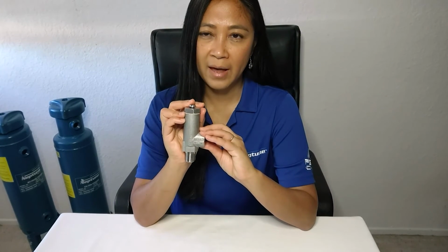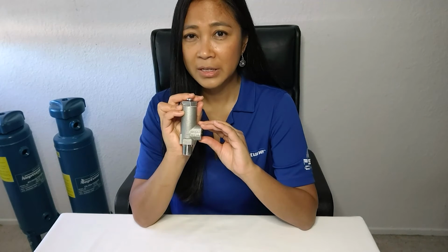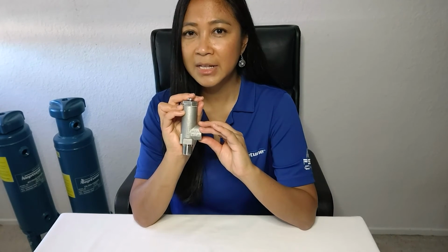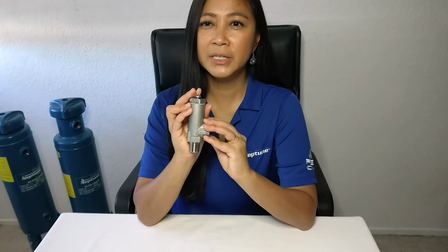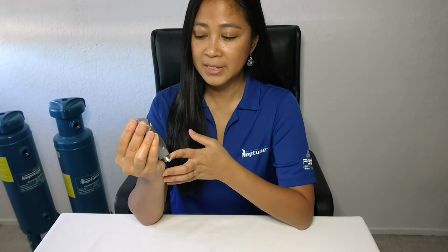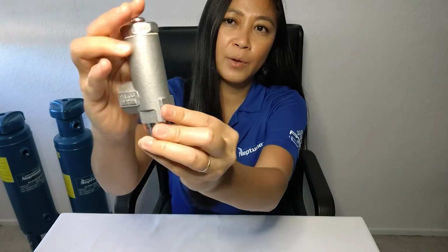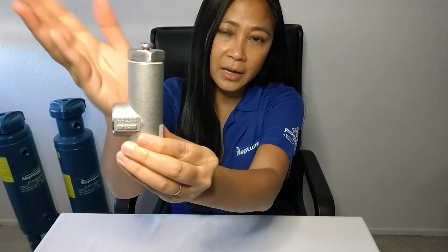As for the specifications of the relief valve, the pressure is available between 30 to 2000 psi. Material is available in 316 stainless steel, Alloy 20, PVDF, and PVC. This particular one, the RV316, that I have in my hand is the RV316-1, where the pressure can be set between 30 to 100 psi. As you can see from here, this one's 316-1, indicating that the pressure is from 30 to 100 psi. At the factory, we can set that when we receive your request based on your setting requirement. And this particular one is set at 75 psi.